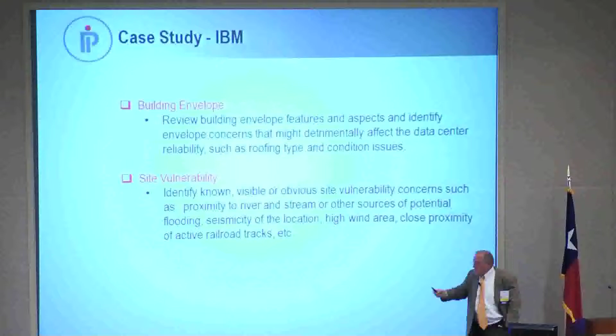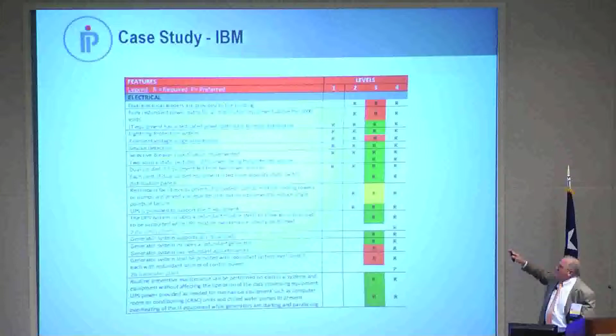In the case of IBM's Tier 3 and Tier 4 facilities, we have a very well-defined list of building elements, electrical, mechanical, and controls, across Tier 1, Tier 2, Tier 3, and Tier 4. It's a very simple audit. We review the facility, and the requirement is either met or not. There's very little gray. The red areas are where you did not meet the Tier 3 requirement, the green are where the requirement was met, and the yellow indicates it was met but with some peculiarity that needed to be resolved.